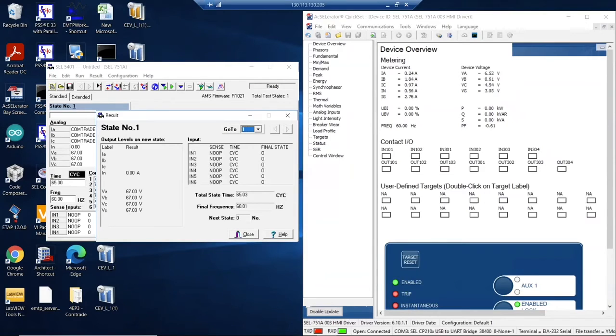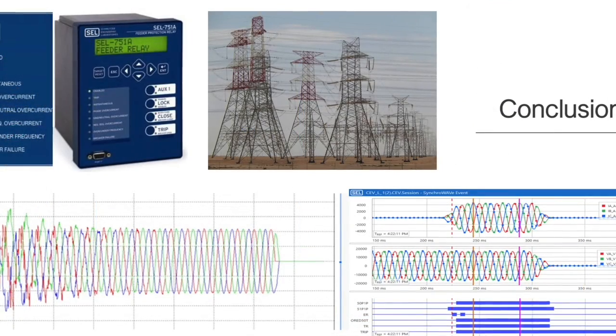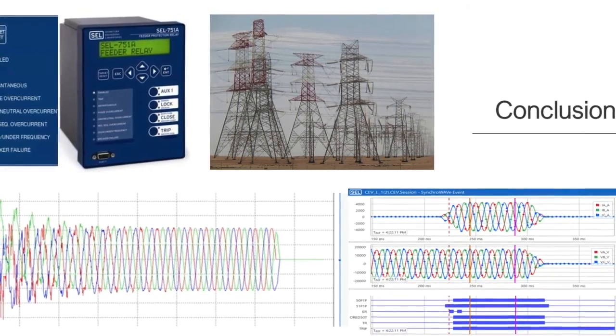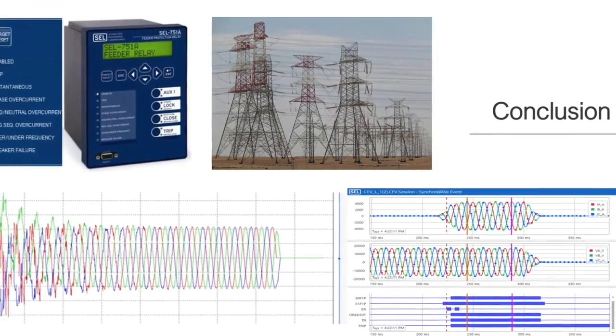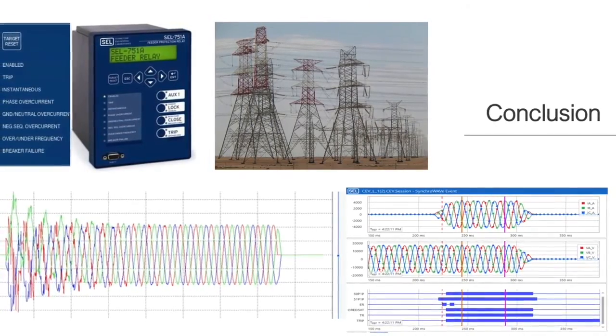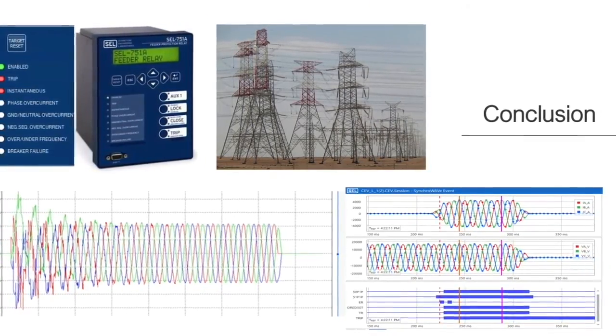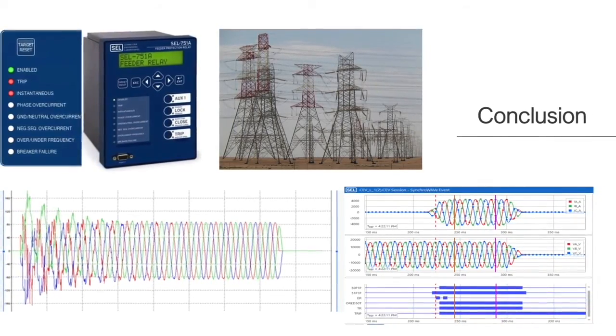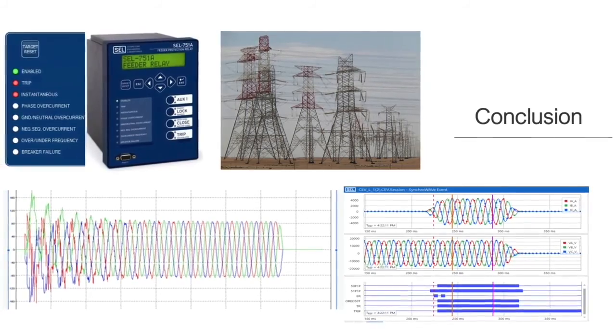Now, I would like to hand over to Shehnaz for the conclusion. Thank you, Melvin. The project is to simulate the three-phase overcurrent fault and generate the COMTRADE file for the fault analysis and uploading on relay. The overcurrent fault analysis is done using Scope View and Syncrowave. It is observed that the fault current is much higher than the load current. The SEL 5401 uploaded the overcurrent fault on the 751 relay.